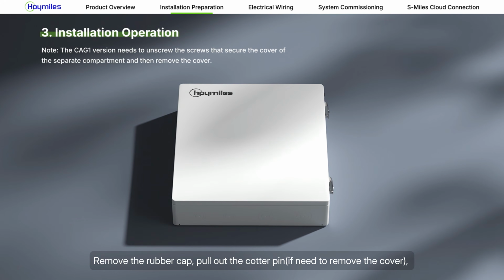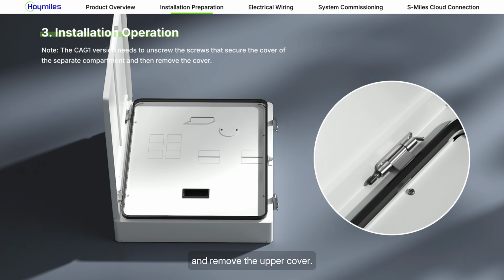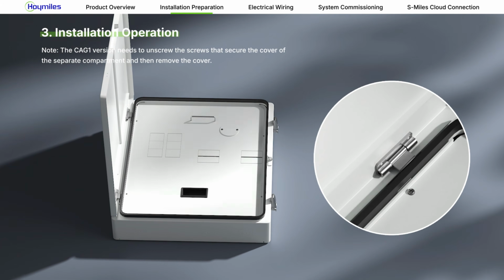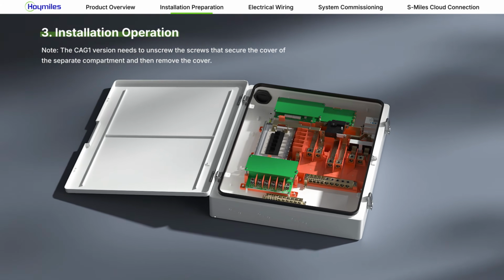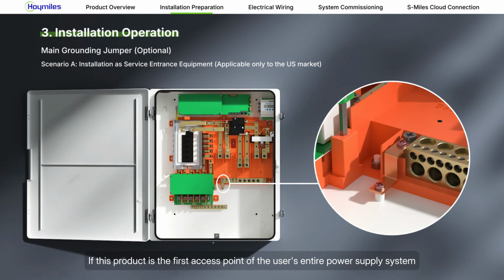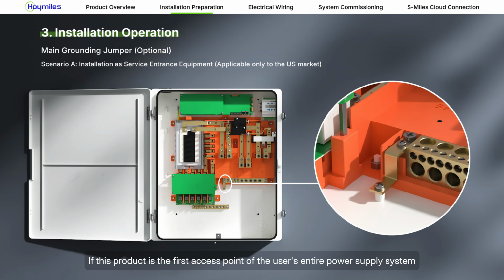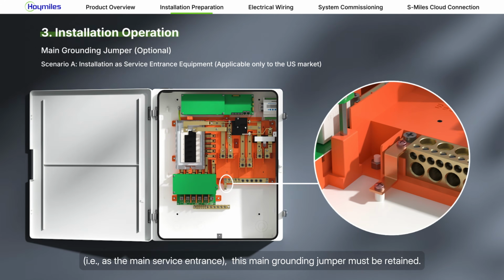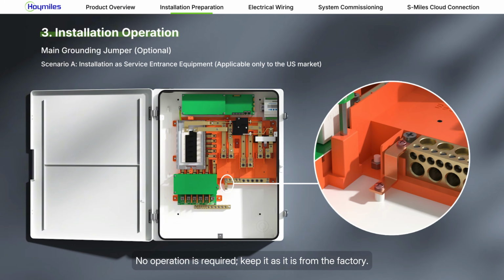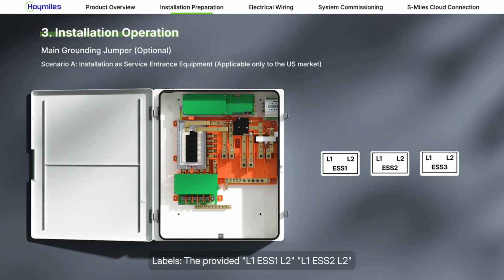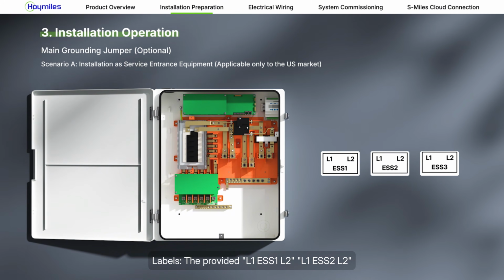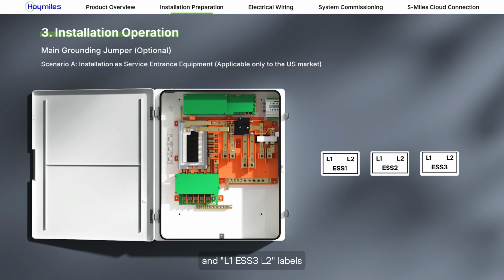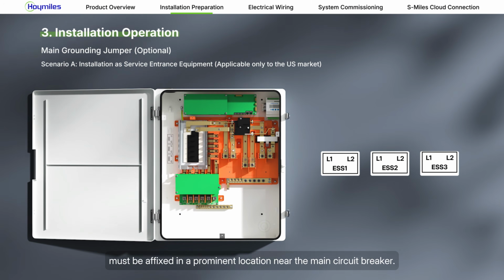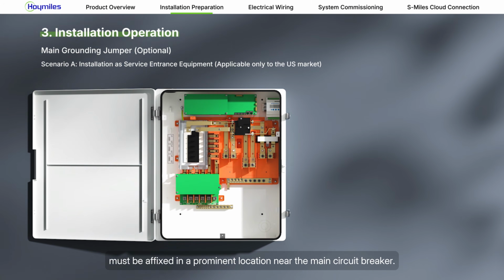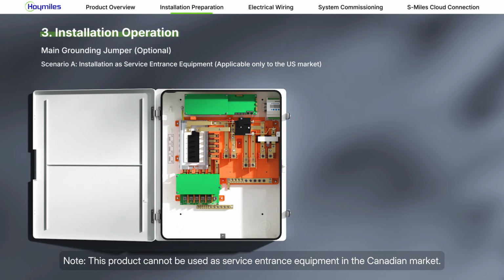Remove the rubber cap, pull out the cotter pin, and remove the upper cover. If this product is the first access point of the user's entire power supply system, this main grounding jumper must be retained. No operation is required. Keep it as it is from the factory. Labels: the provided L1, L2 labels must be affixed in a prominent location near the main circuit breaker. Note: this product cannot be used as service entrance equipment in the Canadian market.